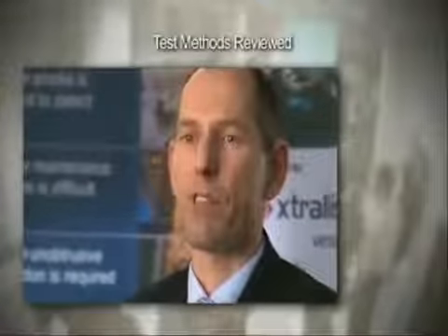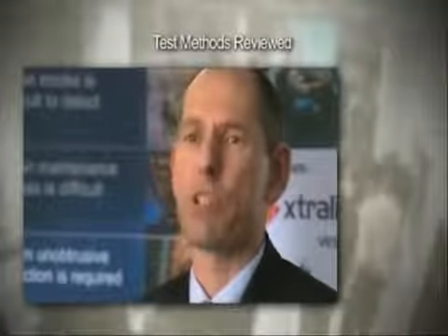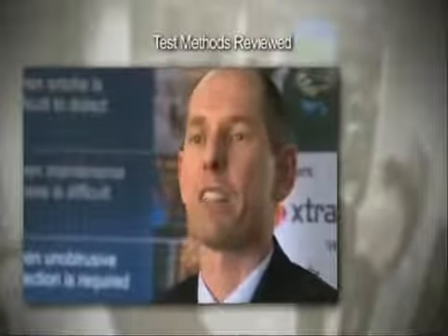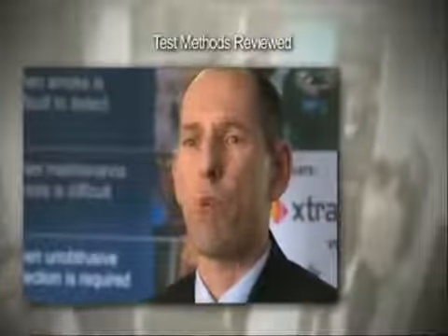The performance of VESDA, as expected, was exceptional. It's able to detect the fire at a very early stage, which, as a designer or as a consultant, I need to know just exactly where its parameters are, where it best works. In a good, clean environment, it can actually smell the smoke really early on, and sometimes that's what we need to do.